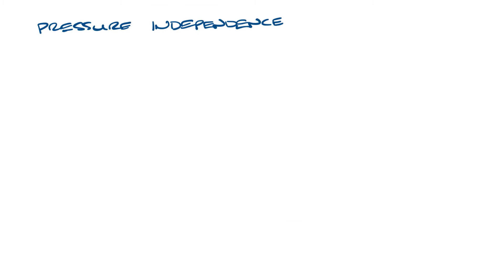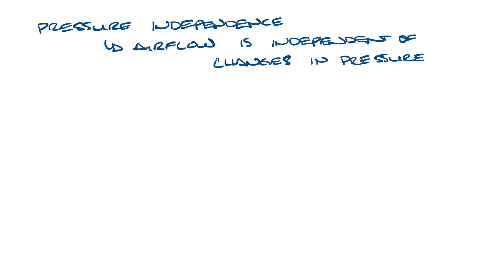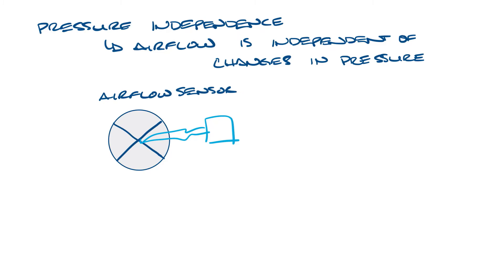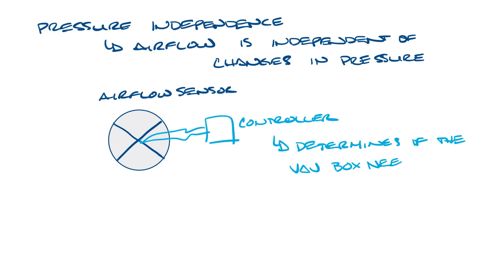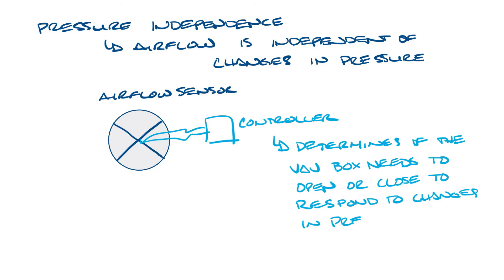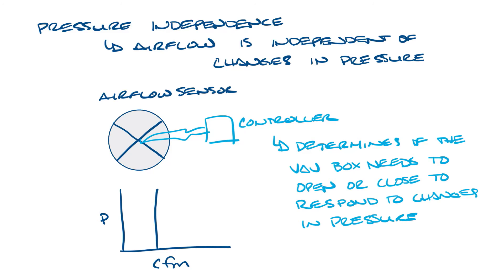Now let's look at pressure independence. In a pressure independent VAV box, the airflow volume is independent of changes in pressure. Pressure independent VAV boxes have flow sensors that measure the pressure in the box and send this information to a controller. If the three VAV boxes in that last example were pressure independent, then when the conference room box opened and the pressure in that duct run went down, the controllers on the other VAV boxes would determine whether to open or close the dampers to maintain the airflow through those boxes. If you were to graph airflow versus pressure in a pressure independent VAV box, it would look something like this, where the CFM stays the same as the pressure changes.